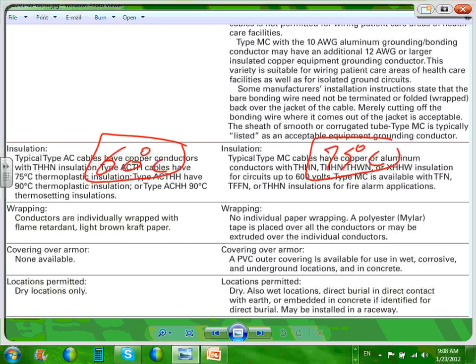Anybody remember why AC is based on the 60-degree column? Because the conductor goes up to number 1. And if the size is up to number 1, you default to where? To the 60-degree column. So that's a major advantage. Look at that, 60-degree column when we size conductor versus 75. That's a major difference, right? So keep in mind, and also, as I told you guys, this comes in 5 kV and 15 kV, so you can use them in medium voltage.